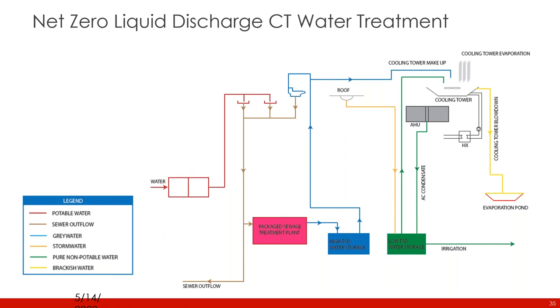So what has happened is that there's developed some recent, relatively last 10 years, technology for cooling tower treatment that really enhances the concentration ratio that you can achieve in the cooling tower by allowing very, very, very high total dissolved solids in the cooling tower water. So basically what happens is this. The first thing that happens is that the makeup water is softened.